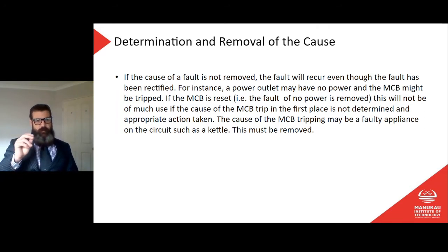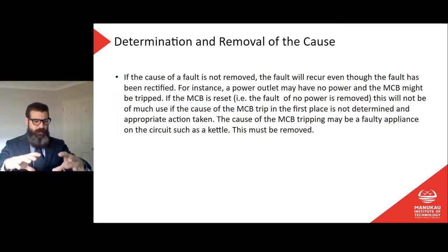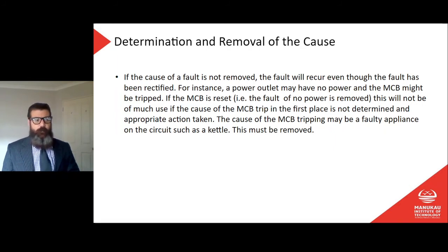Now what I say there is, don't guess, but remember that if you go, I think it might be that circuit board, replace one thing at a time. Do one thing at a time. If you're rectifying at that point, if you go, okay, well, I'm down to, it's one of these 3 components, but I'm not sure which one. So then you're going to rectify by trial and error, which is valid. I mean, I'm not going to rectify by trial and error if there's 89 things that might be wrong. I need to bring that down.